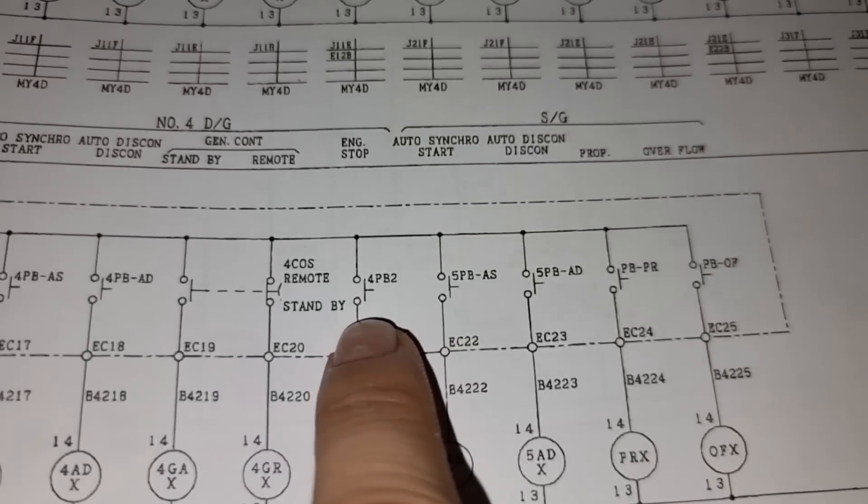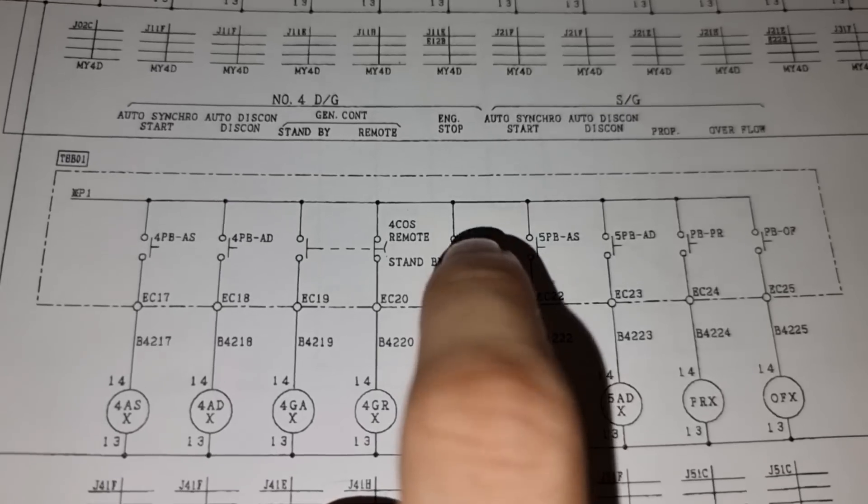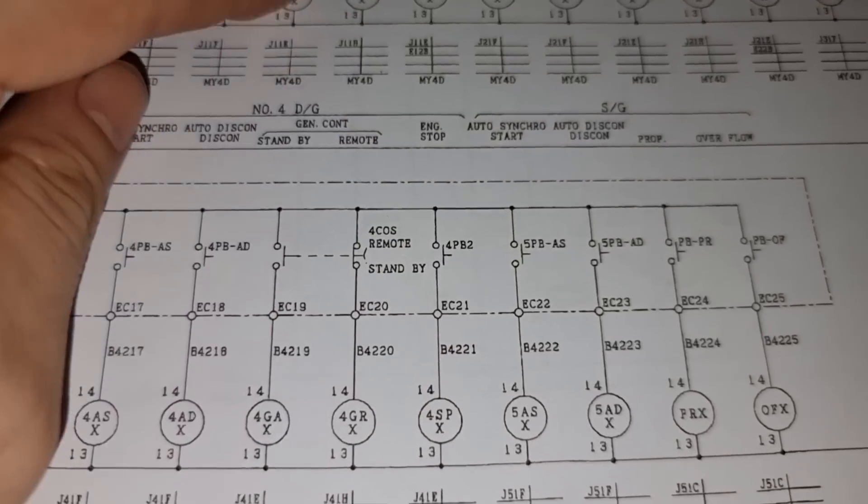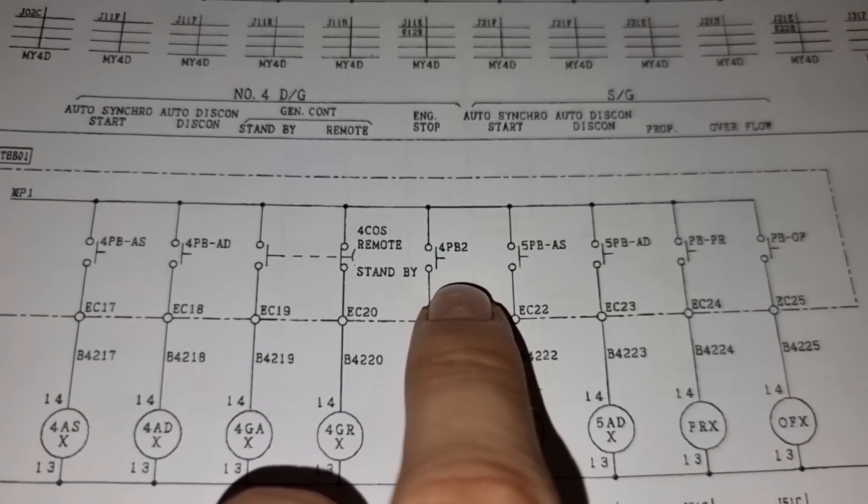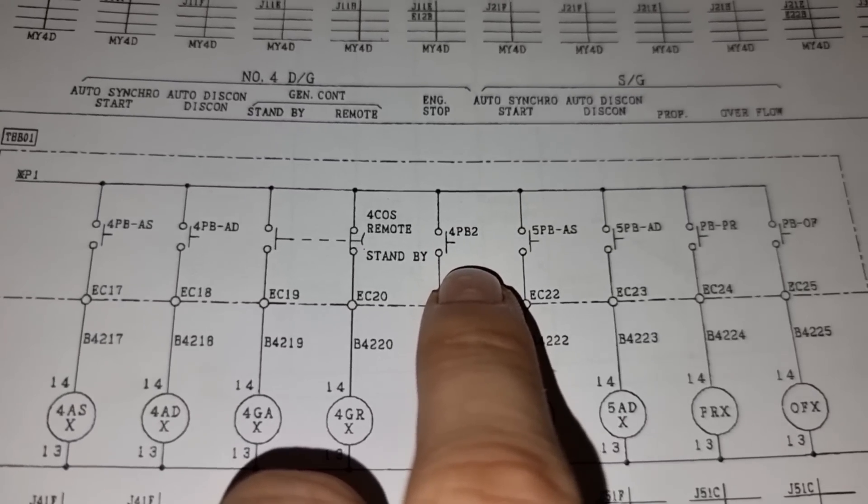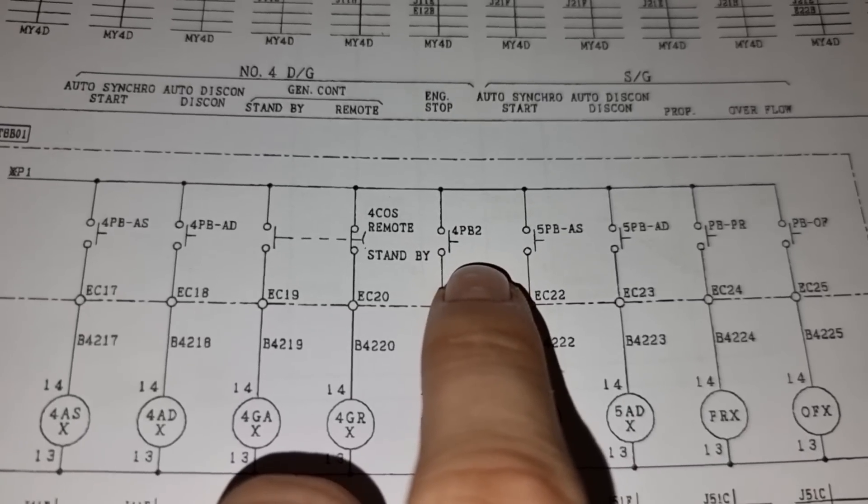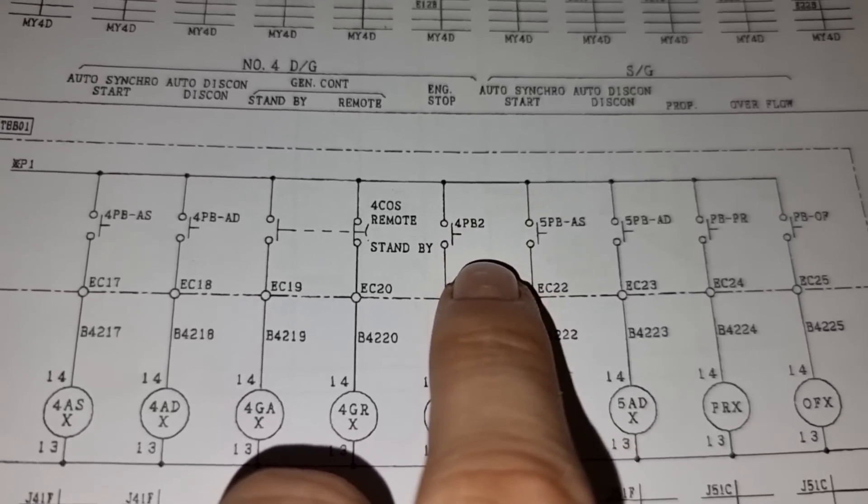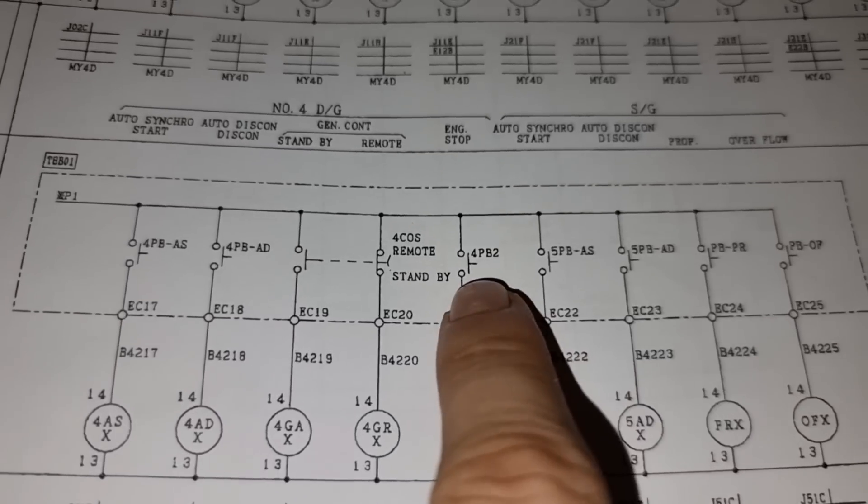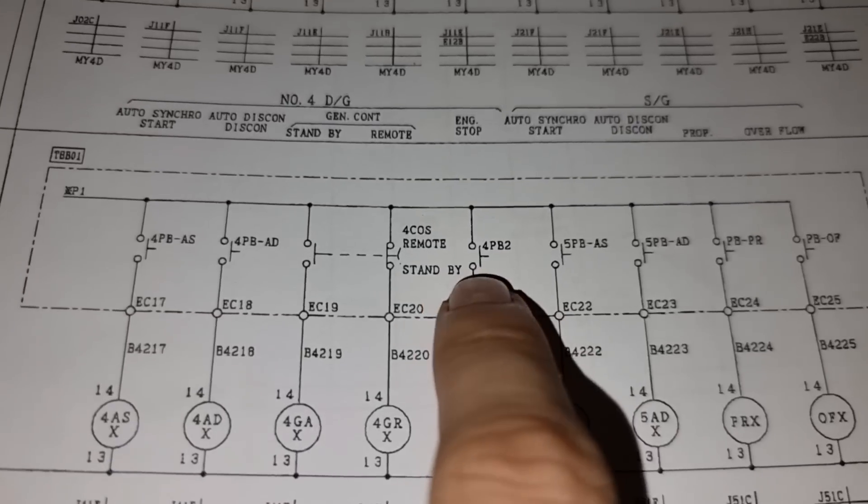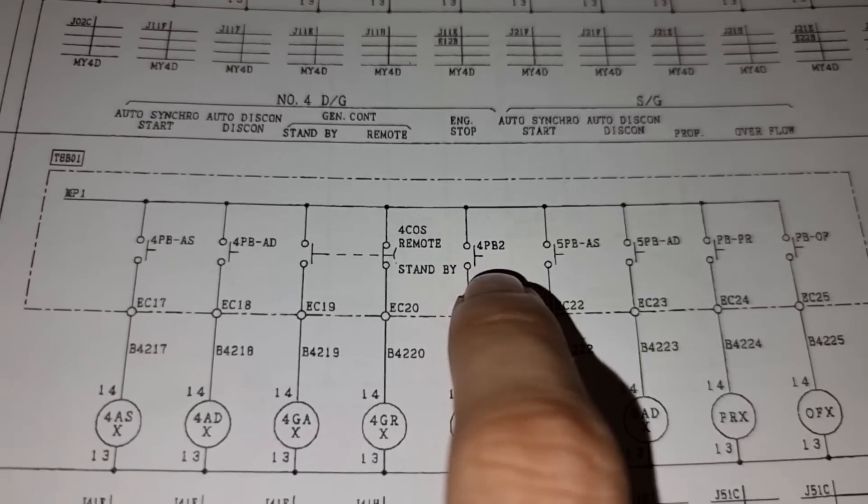And this is the one that controls our whole engine stop, which is being controlled by the controller or the module of our PMS card. Like if we press the stop command onto our computer, this should stop, that should be processed by the PMS card and activate the 4SPX. It means that that command is not closing this 4PB2.